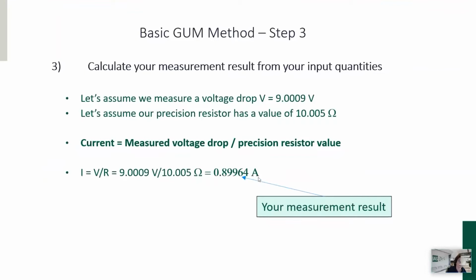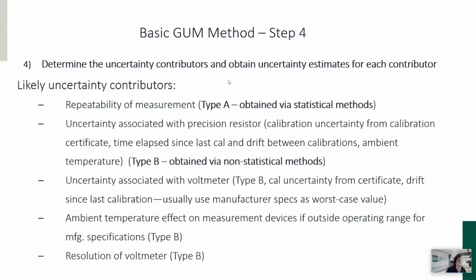So the next step is to determine what kind of uncertainty is associated with this result, given in amps here. First we have to figure out what contributors could contribute to the uncertainties for each input. One might be repeatability of measurement, the uncertainty associated with the precision resistor. We know there's always a calibration uncertainty, the time elapsed since the last calibration, drift between calibrations, ambient temperature, uncertainty associated with the voltmeter, the ambient temperature effect on measurement devices, and the resolution of the voltmeter. This is just to mention a few.